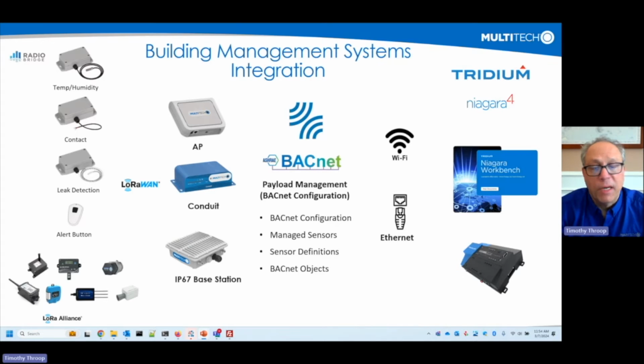To test this environment out, you can also use something called Yabe, which is basically a test tool to see if you're getting BACnet traffic from the gateways and from the sensors. But to incorporate this fully into a building management system, you need something like Niagara to really see its power and capability.